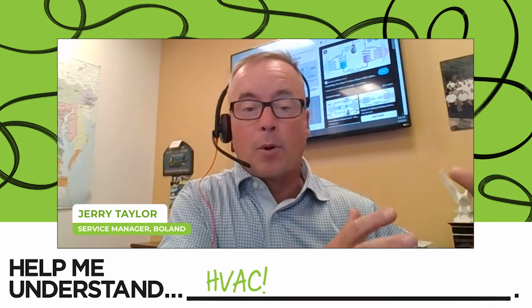So consider a commercial office building. The sun comes up in the east and you have that huge solar load, and those people are getting cooked. While on the west side of the building, it's still shaded. Maybe not everybody has shown up to work yet, so you don't have the lights and the computers and all the other heat loads. So they don't need as much air conditioning. So in a VAV system, we tell the unit on the roof, spit out 55-degree air all day long. And then we have air valves in the building that will open and close to maintain the space temperature.